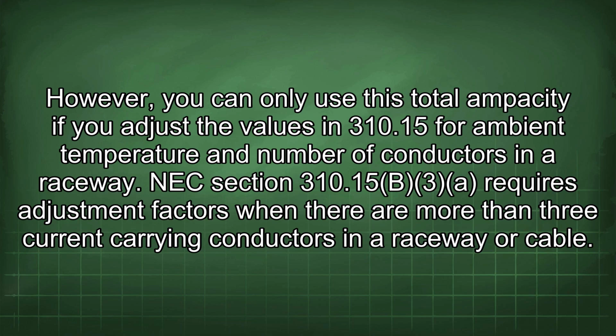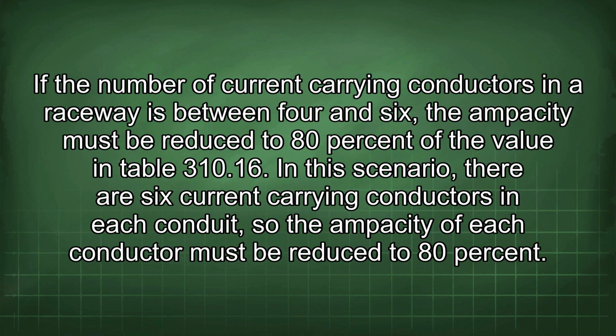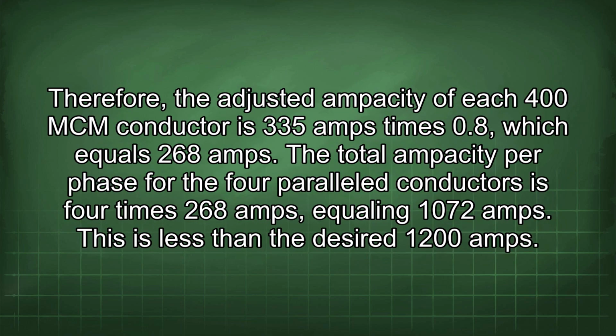310.15(B)(3) requires adjustment factors when there are more than 3 current-carrying conductors in a raceway or cable. If the number of current-carrying conductors in a raceway is between 4 and 6, the ampacity must be reduced to 80% of the value in Table 310.16. In this scenario, there are 6 current-carrying conductors in each conduit, so the ampacity of each conductor must be reduced to 80%. Therefore, the adjusted ampacity of each 400 kcmil conductor is 335 amps times 0.8, which equals 268 amps.